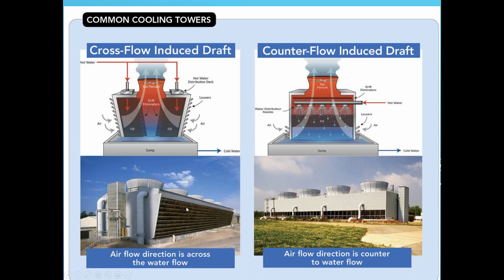In this case, this distance is approximately 30 feet from the curb up to the top of where the hot water basin is. You can also see where the return riser is coming up to that elevation. Another way to distinguish a cross-flow tower is that the end walls are sloped to conform to the airflow, because you have the higher velocities at the top and the lower velocities at the bottom.